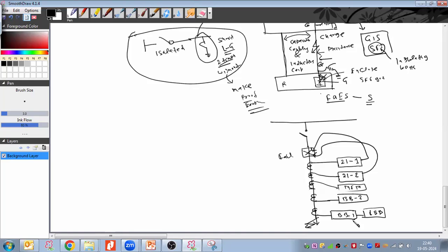Then what will happen? This bus bar protection will operate, the LBB will operate, right? But this LBB will operate after how much delay? 100 milliseconds, right? After 100 milliseconds, it will issue the trip command to the breaker.